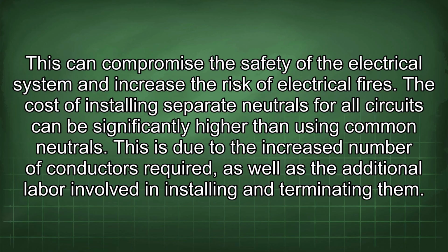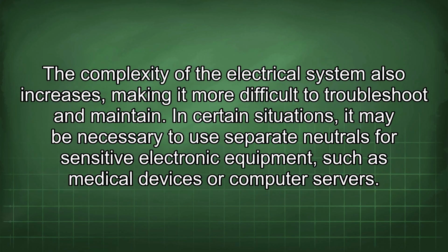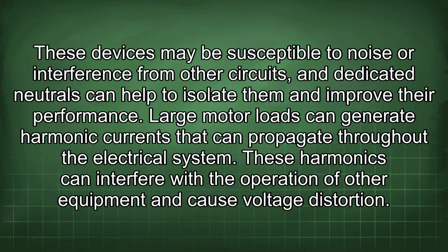The cost of installing separate neutrals for all circuits can be significantly higher than using common neutrals. This is due to the increased number of conductors required, as well as the additional labor involved in installing and terminating them. The complexity of the electrical system also increases, making it more difficult to troubleshoot and maintain. In certain situations, it may be necessary to use separate neutrals for sensitive electronic equipment, such as medical devices or computer servers. These devices may be susceptible to noise or interference from other circuits, and dedicated neutrals can help to isolate them and improve their performance.